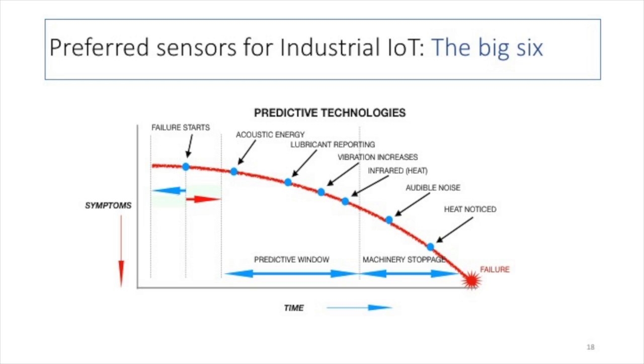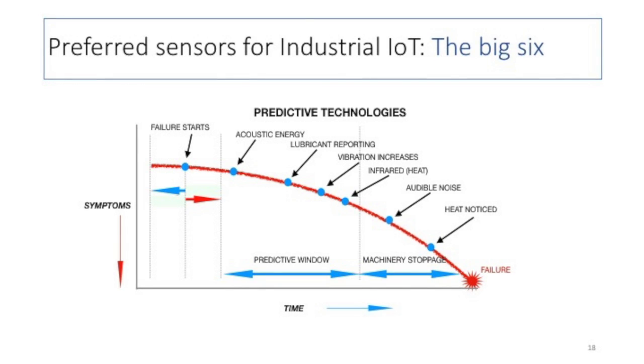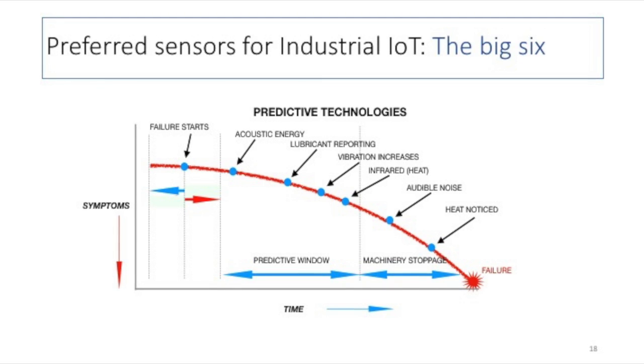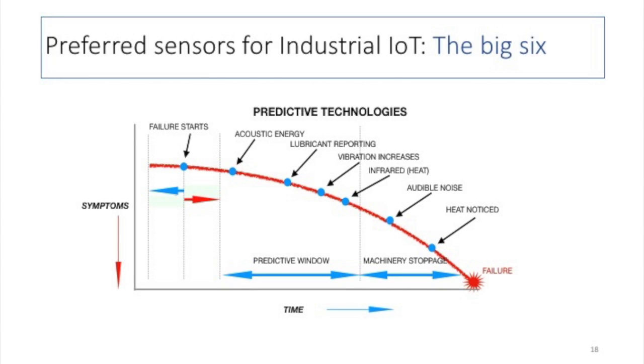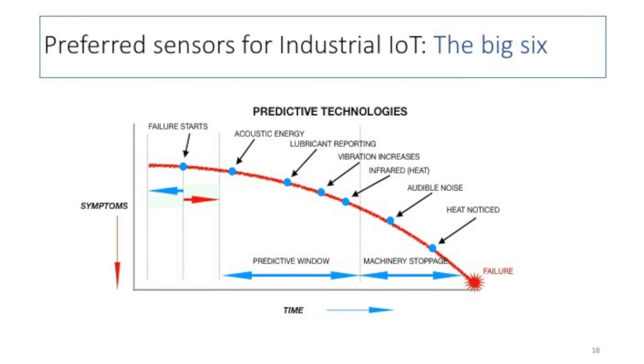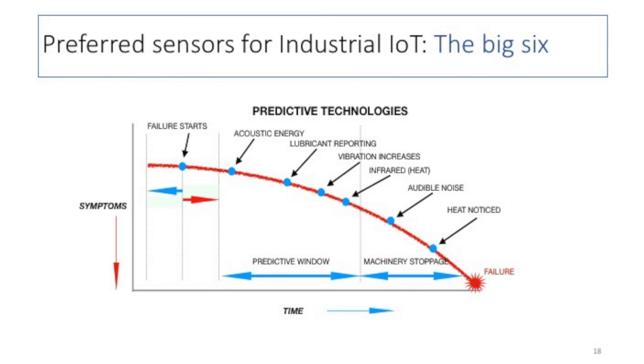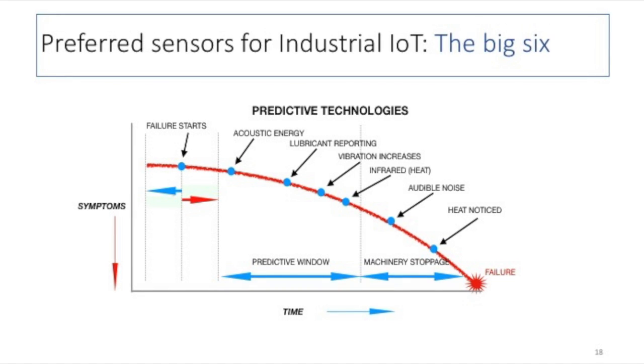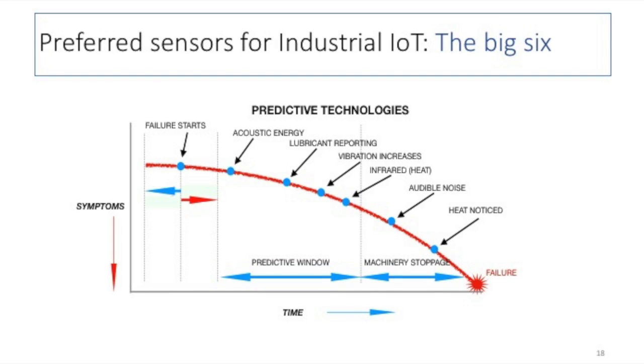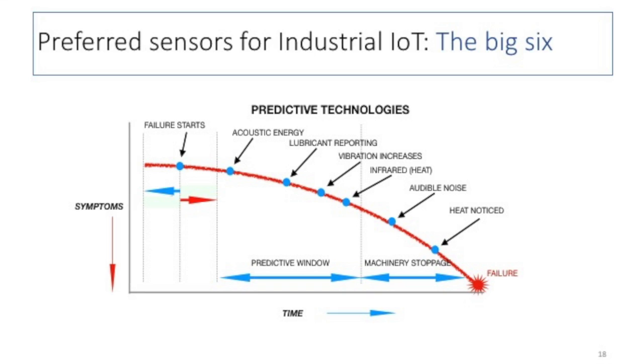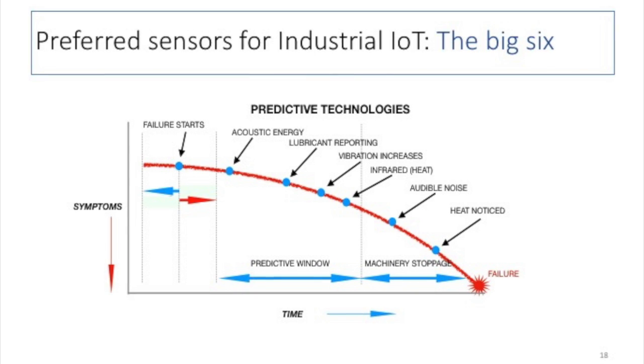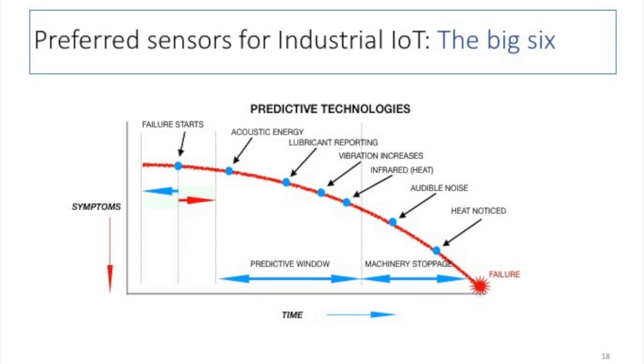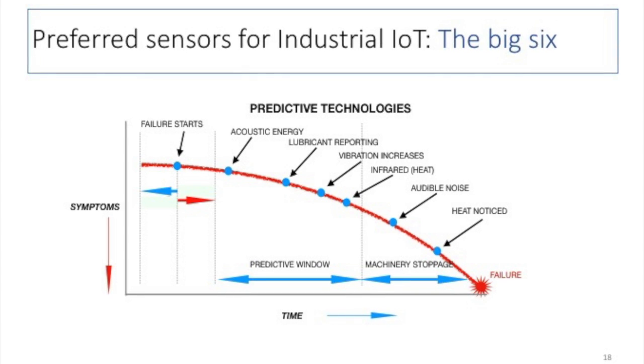The first sensor in our list, at the left, is acoustic energy, which measures acoustic emission in the ultrasound spectrum. That measures material stress in machinery and gives the earliest warning of failure probability. The second and third sensors are very close together: in machinery with lubricants, measuring lubricant contamination gives a good warning before something bad happens. Vibration is a very common sensor used widely in machinery monitoring, although sometimes, particularly if the sensor is not very good, the warning comes way too close to the failure.